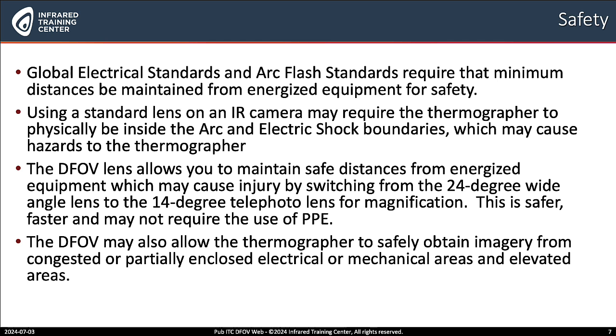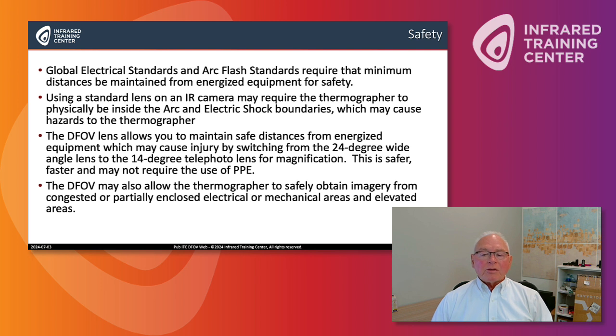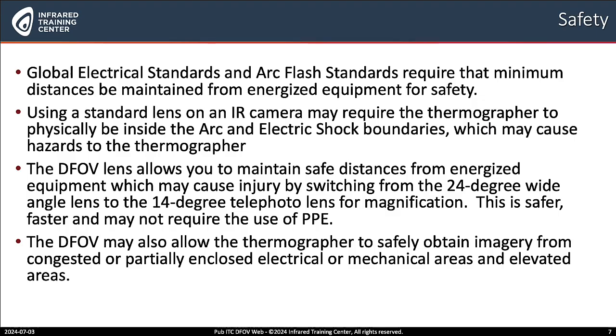What about safety? Global Electrical Standards and arc flash standards require that minimum distances be maintained from energized equipment for safety. Using a standard lens on an IR camera may require the thermographer to physically be inside the Arc and Electric Shock boundaries, which may cause hazards to the thermographer. The DFOV lens allows you to maintain safe distances from energized equipment by switching from the 24 degree wide angle lens to the 14 degree telephoto lens for magnification. This is not only safer, it's faster, and in some situations may not require the use of PPE.